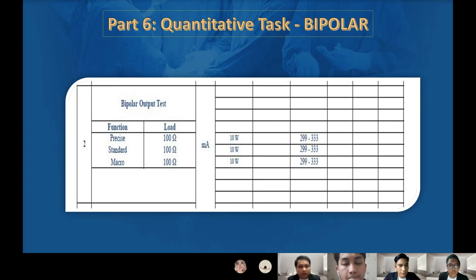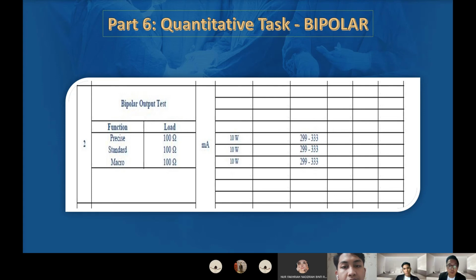Okay, so I will continue the presentation. For quantitative tasks, as you know, we have two: monopolar and bipolar. I will explain more about the bipolar output test. What is the bipolar output test? It is where the current flows from one tip to the other through the tissue held between the forceps. As bipolar uses lower voltage, less energy is required, but because it has a limited ability to cut and coagulate large bleeding areas, it is more ideally used for procedures where tissue can be easily grabbed on both sides by the forceps.